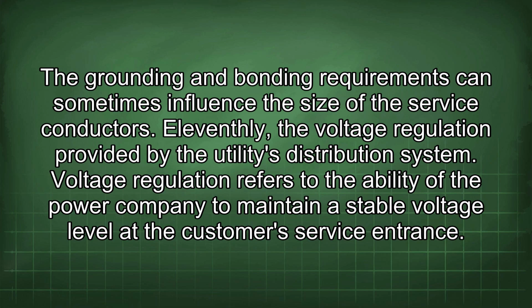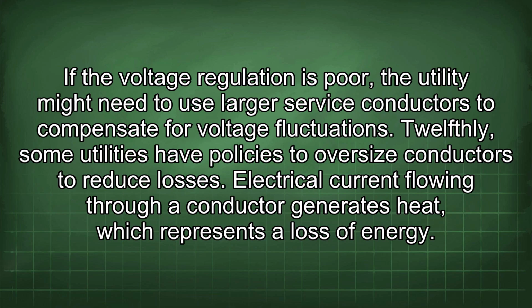11thly, the voltage regulation provided by the utility's distribution system. Voltage regulation refers to the ability of the power company to maintain a stable voltage level at the customer service entrance. If the voltage regulation is poor, the utility might need to use larger service conductors to compensate for voltage fluctuations. 12thly, some utilities have policies to oversize conductors to reduce losses.